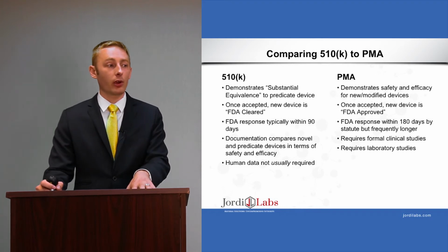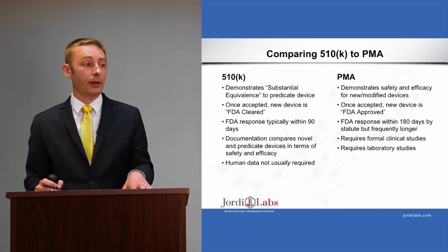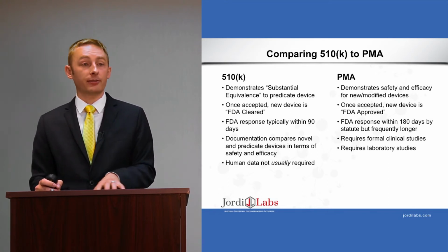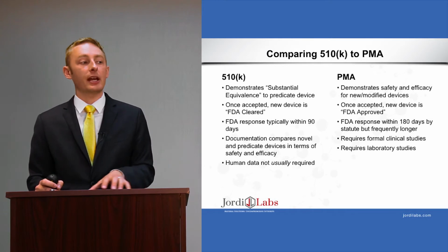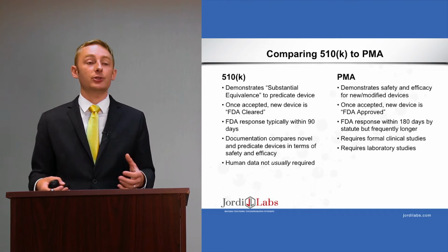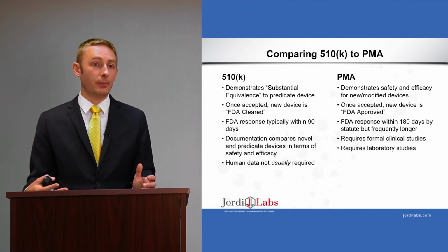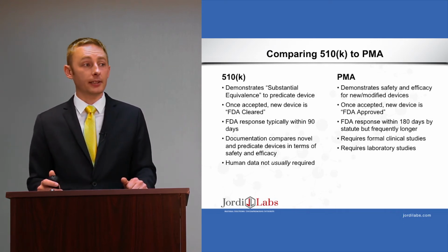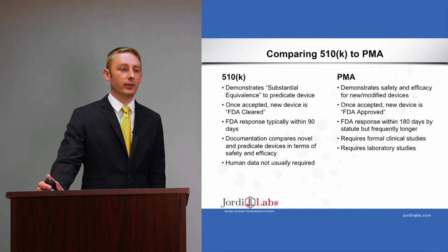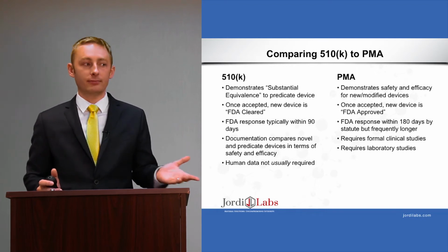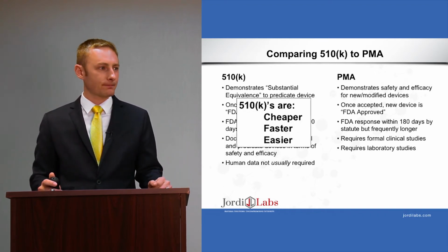The documentation for a 510K really only compares the novel device, your new device, with the predicate device in terms of safety and efficacy. And so for the PMA, in contrast, you have a formal clinical study that involves patient populations. It also requires laboratory studies. The 510K doesn't necessarily require human data. And so there's a big advantage in terms of going through the 510K process as opposed to the PMA. In summary, 510Ks are cheaper, easier, and faster.